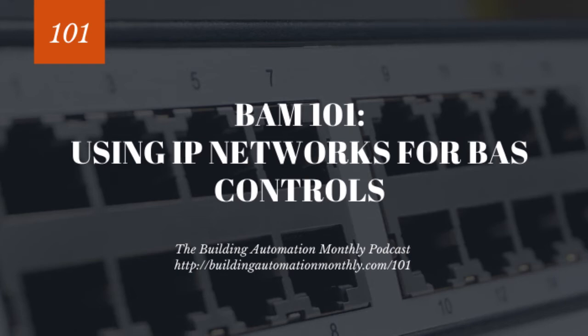I've heard this might be a manufacturer field controller issue, not an IP issue. The network interface cards on these field controllers have to be powered for the signals to continue across the wire. Unlike MSTP, which is self-powered, with IP, if the power goes down on the controller in a daisy chain or ring pattern, does it lose communication? Is that a manufacturer thing? Am I even making sense?